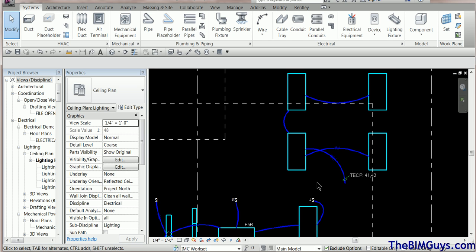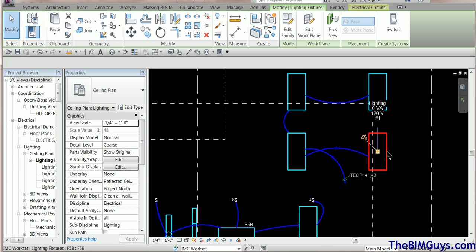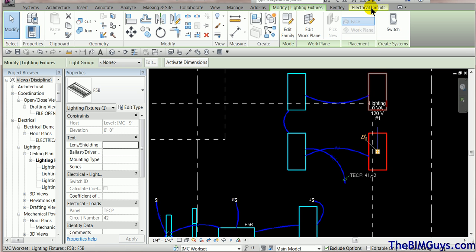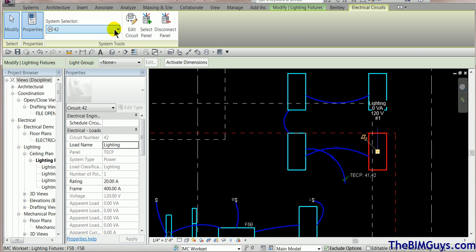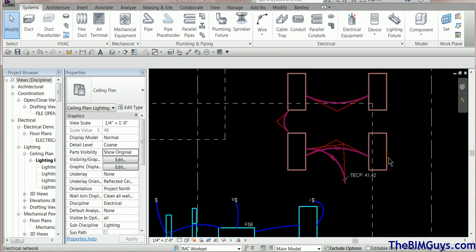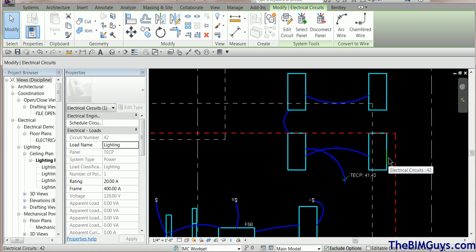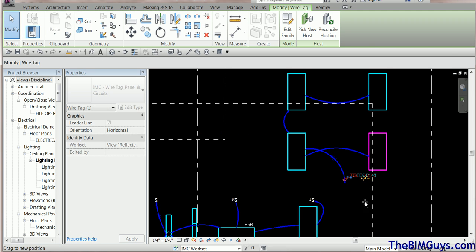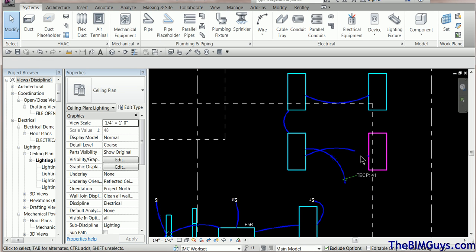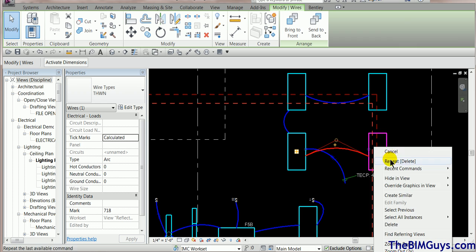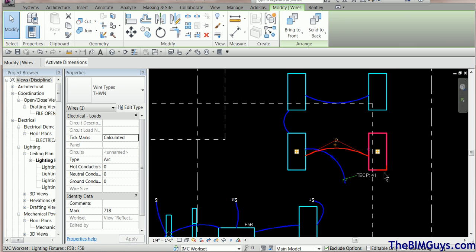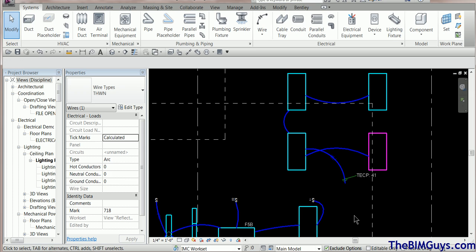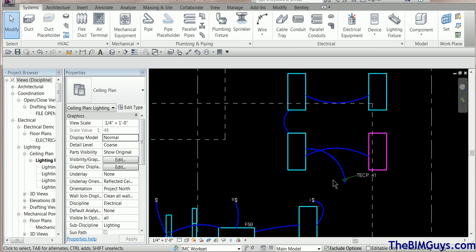That's a good tip to understand how those work. If you don't want to see the wire ticks, you can turn those on and off, but that's the proper way. Sometimes what happens is you'll have an element that's not on a circuit. If I go to Electrical Circuits tab, I can tab over an element, select the circuit, and hit Delete — I'm not deleting the fixture, just the circuit. Now it only has one fixture on it, causing weird behavior. Make sure your elements are circuited.